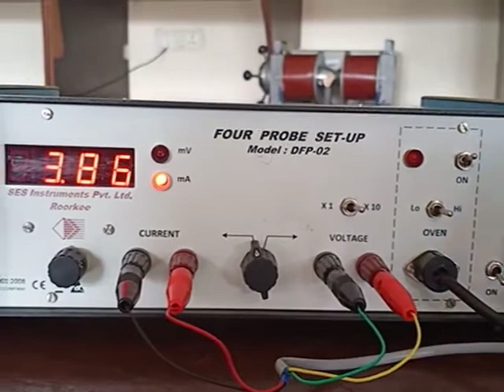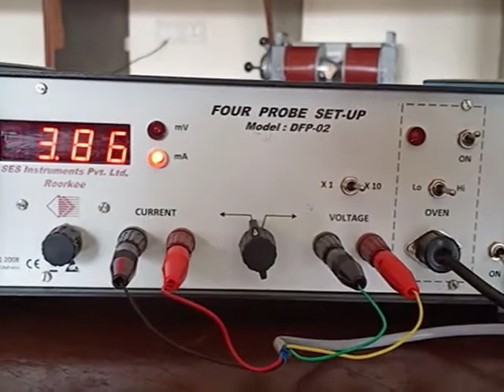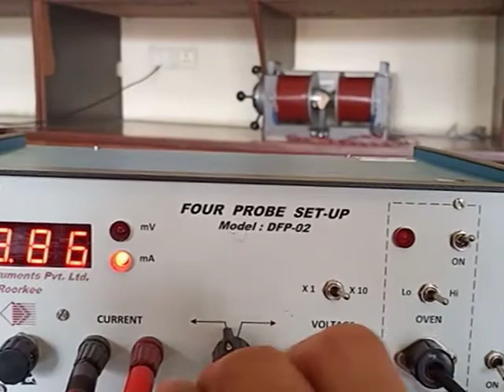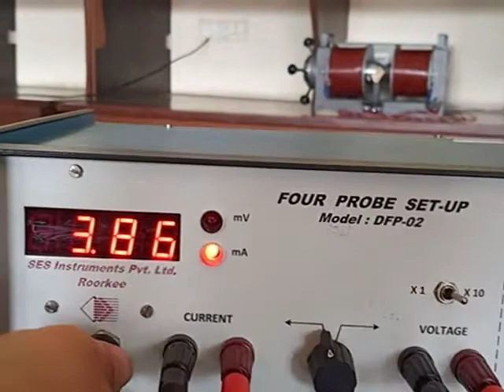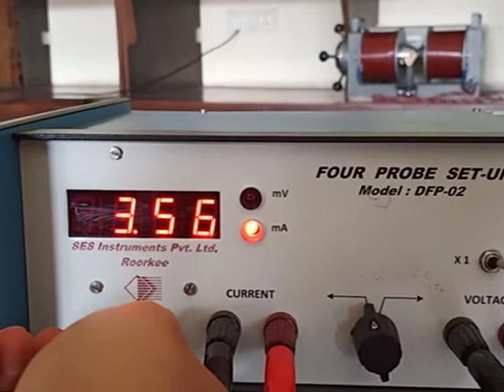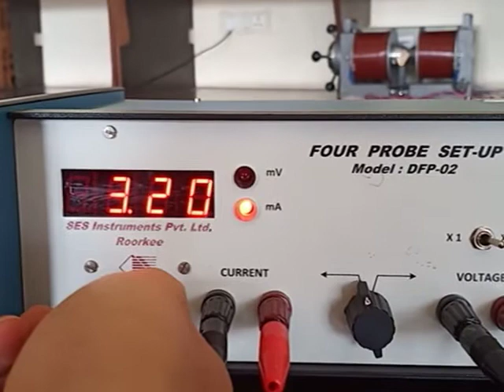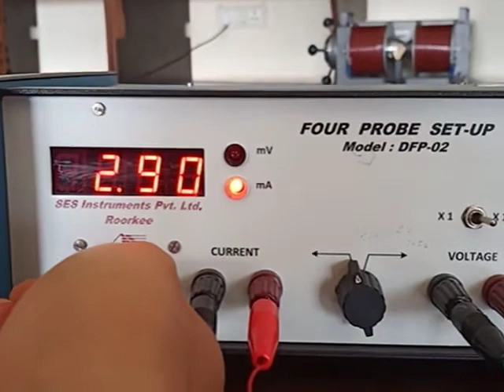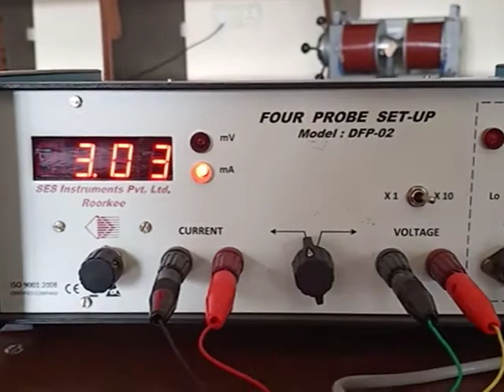We have to flow the current for a longer time. This experiment runs for 2 hours, so we cannot flow a high current through the crystal. If you switch this knob towards the current section, the current is 3.86, and from this knob we can control the value of the current. Let us suppose I set the current near about 3 milliampere. This knob is very delicate. Now it is 3.04, that is fine.